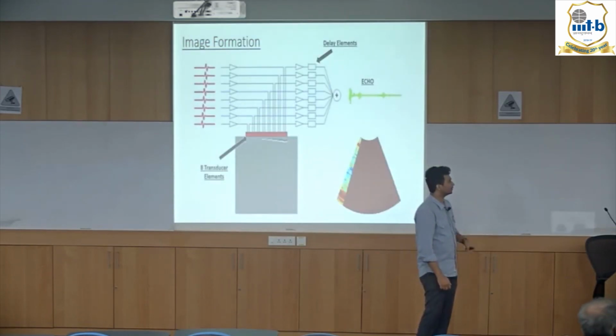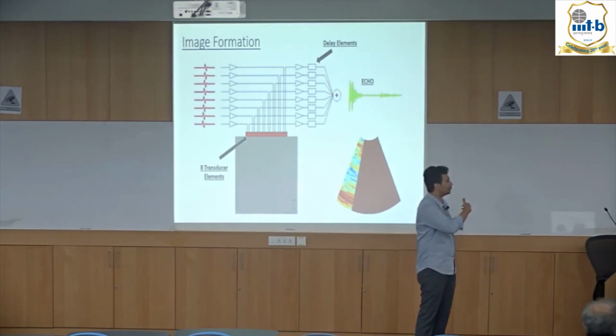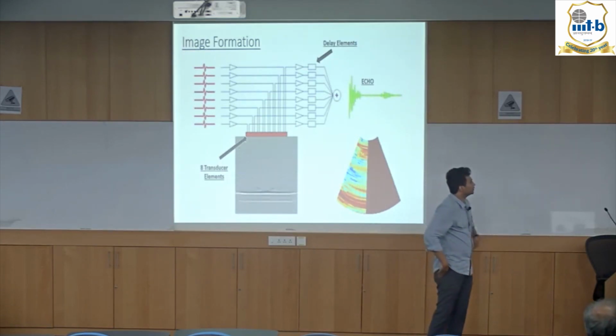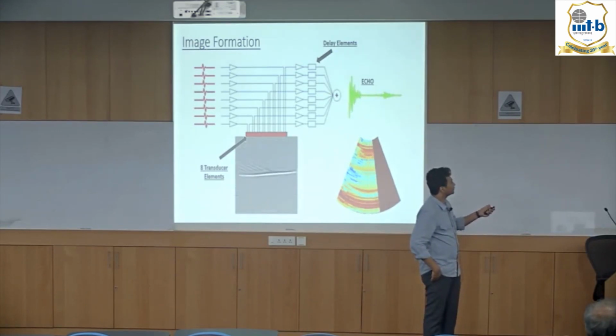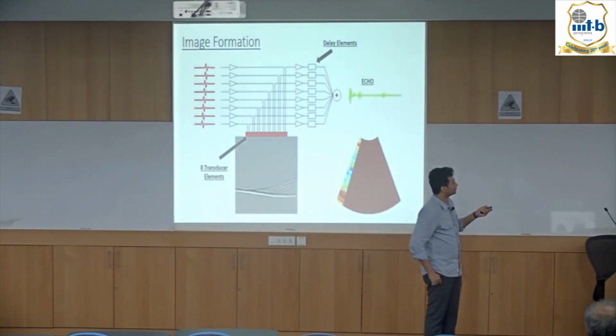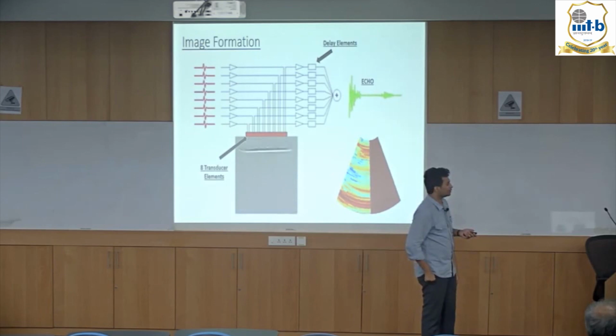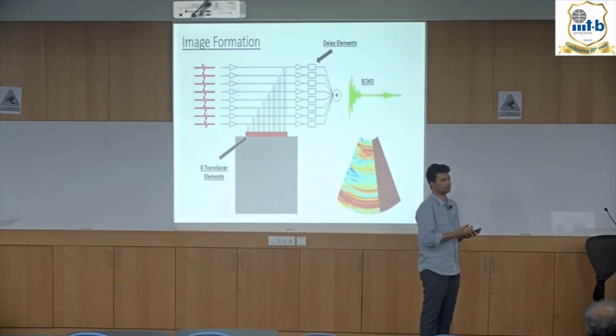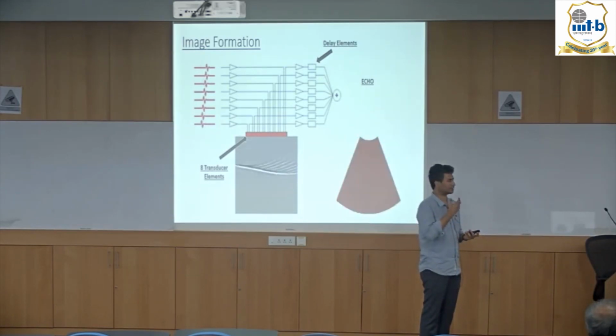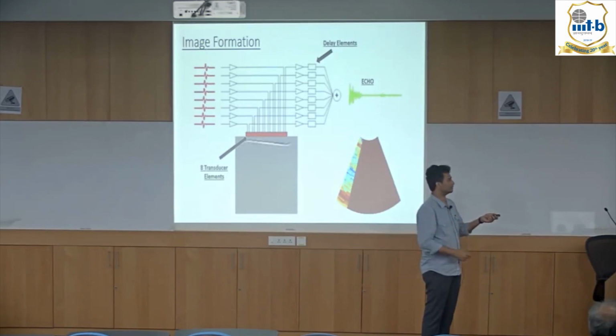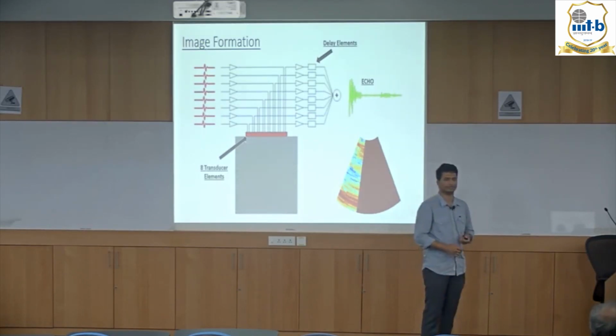This is a small video which will show how an image is formed. You can see here these are the delay values. The pulses are delayed by a little bit for every echo that is acquired. As this is being done, each echo acquired is a line in the image. Typical ultrasound systems nowadays have frame rates greater than 100, 200, so each image is happening so fast. This is all possible because of the FPGAs and the signal processing which goes on.